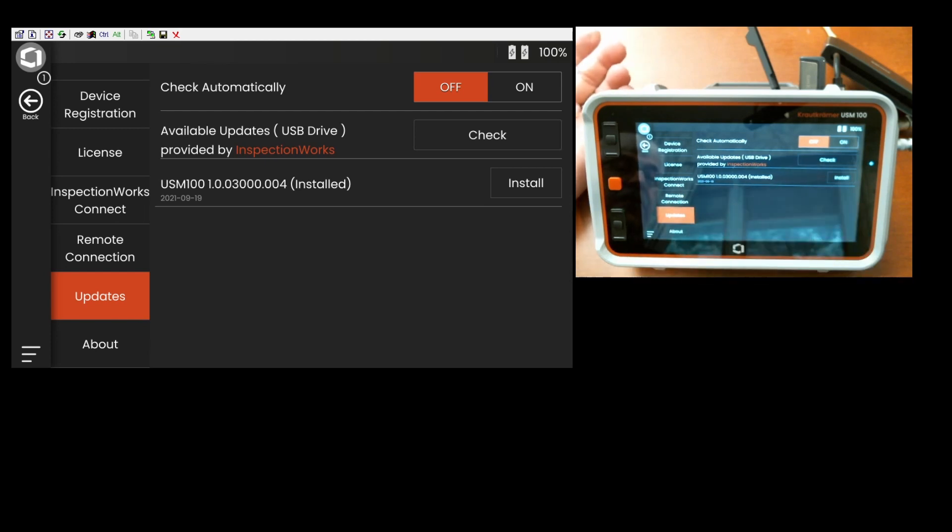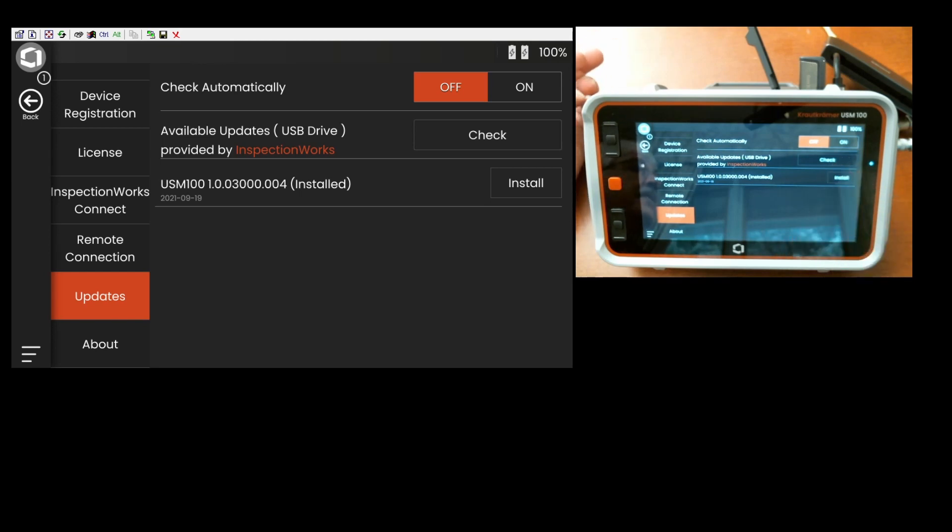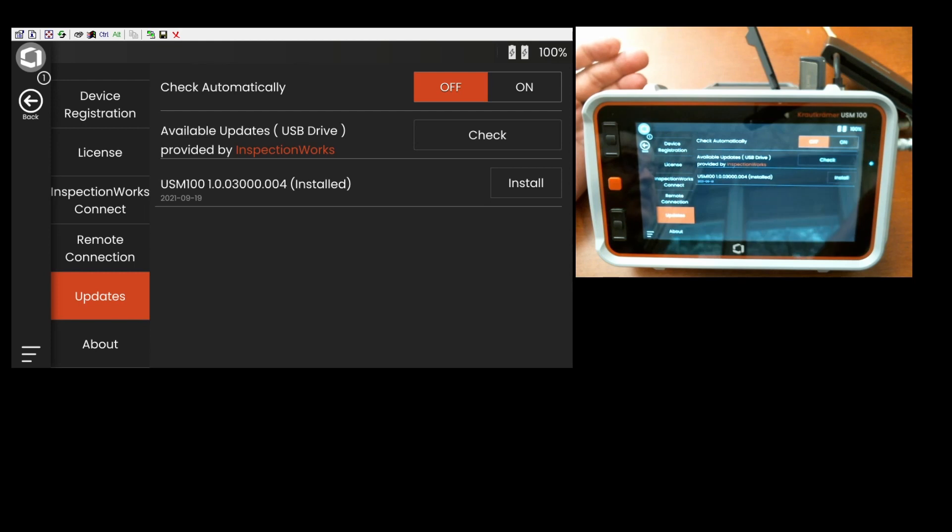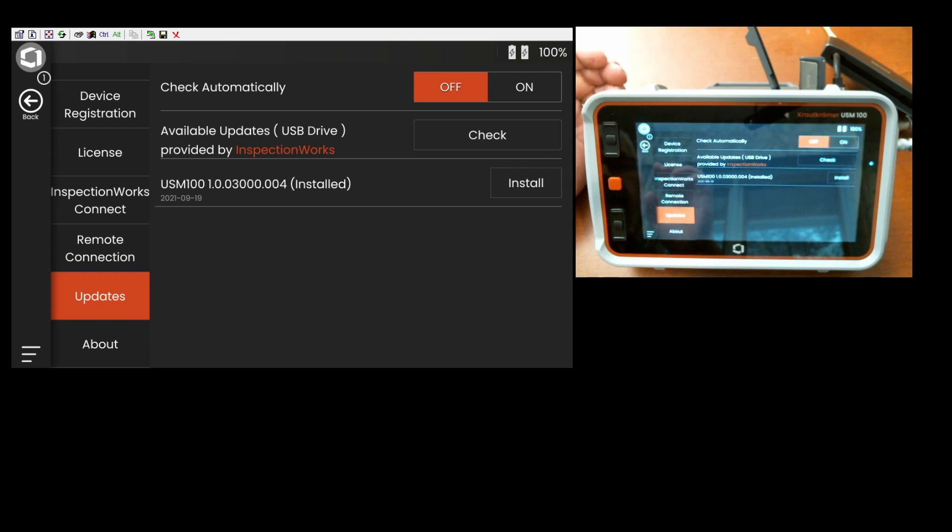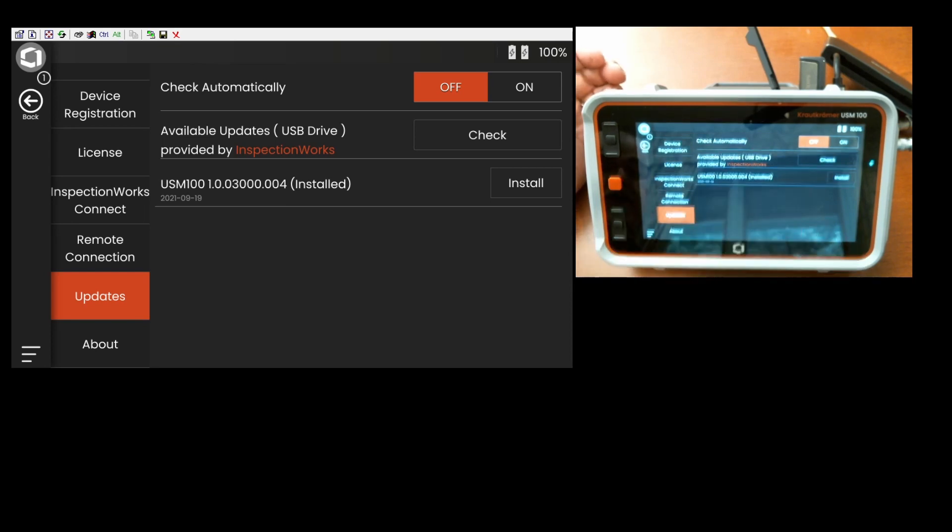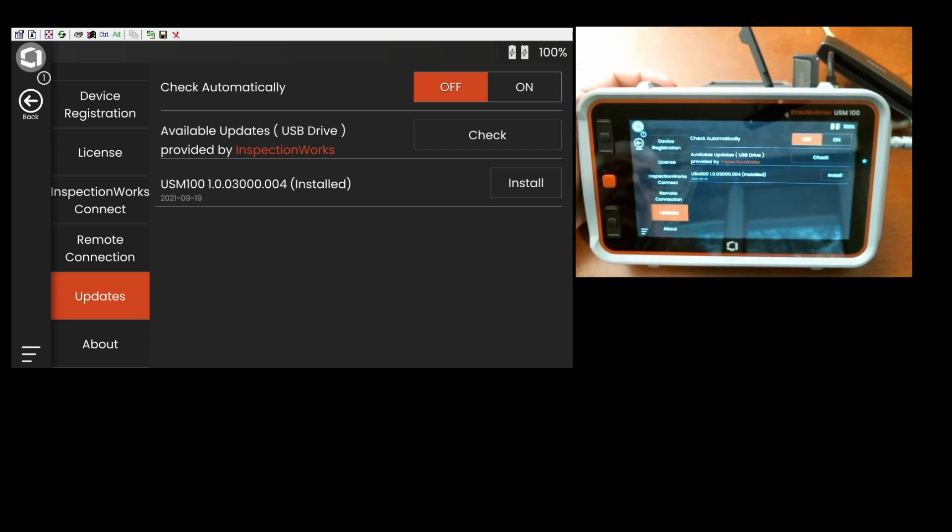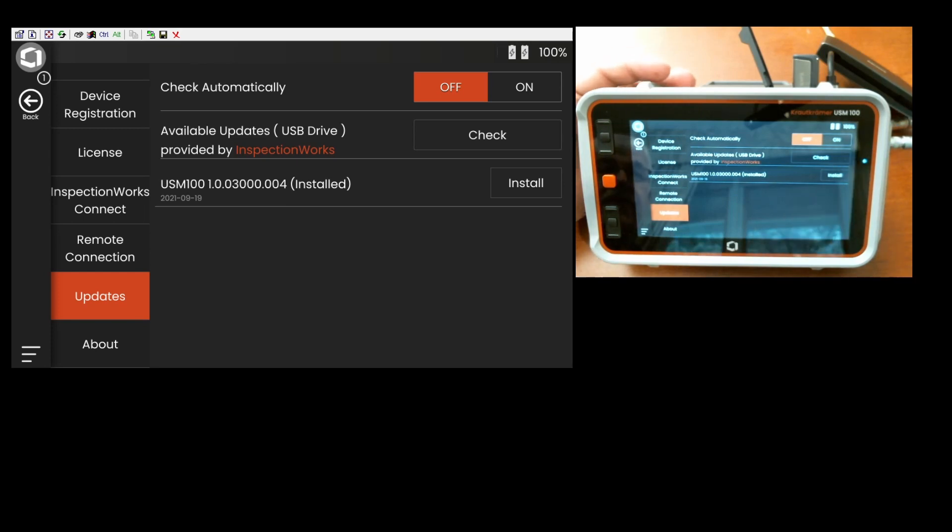So if there was a newer version on the stick, it wouldn't tell me that it's already installed. The instrument will allow me to overwrite the installation if I so choose. If I touch install now, it will kick off the installation process. I'm not going to do that right now because it will sever the connection to the computer. We won't get to see a lot of what happens anyway. But what will happen is it will go through about 30 seconds to a minute of downloading and analyzing the update file. Then it will kick off the installation process. So the windows that you see on the screen will change. It will show progress bars. It is best if you're plugged into the charger or have a fully charged battery before you begin the installation process. You don't want the instrument to run out of power halfway through a software update. So I usually have my instrument plugged into the charger and connected to mains when I do this.